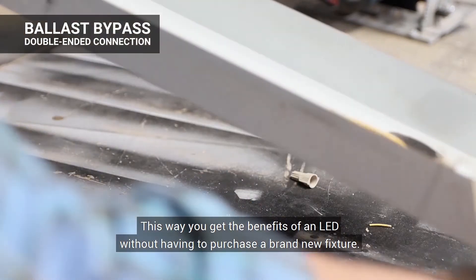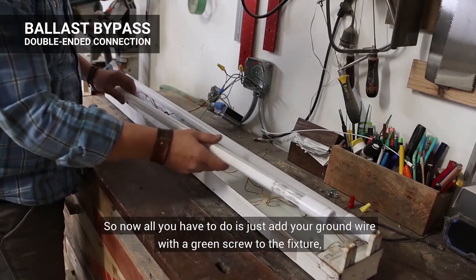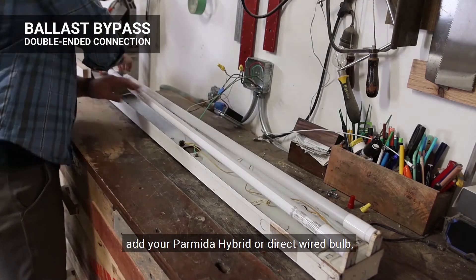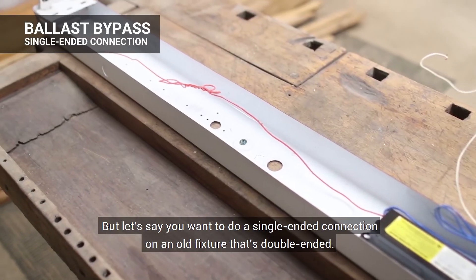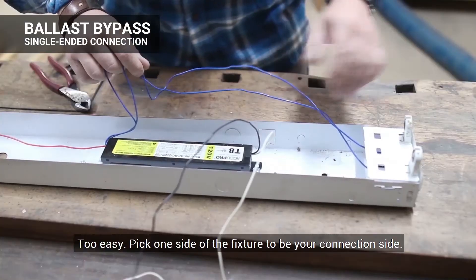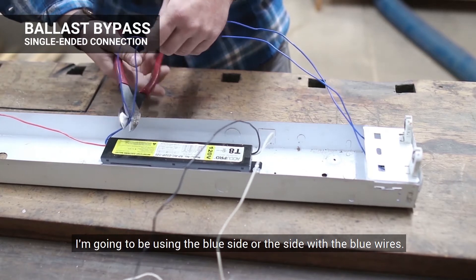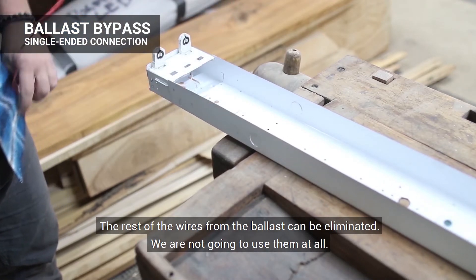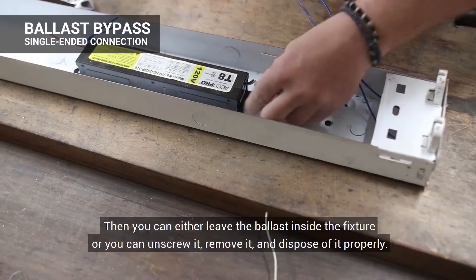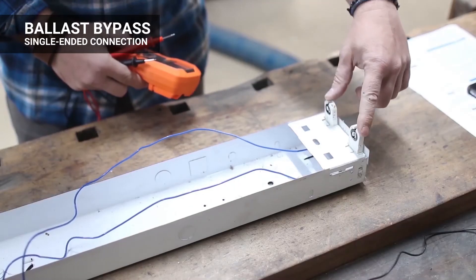This way you get the benefits of an LED without having to purchase a brand new fixture. Add your ground wire with the green screw to the fixture, add your Parmida hybrid or direct wire bulb, and you have double-ended LED brightness. But let's say you want to do a single-ended connection on an old fixture that's double-ended — too easy. Pick one side of the fixture to be your connection side; I'm going to be using the side with the blue wires. Cut them off on that side long enough so you can work with them. The rest of the wires from the ballast can be eliminated — we're not going to use them at all. You can either leave the ballast inside the fixture or unscrew it, remove it, and dispose of it properly.